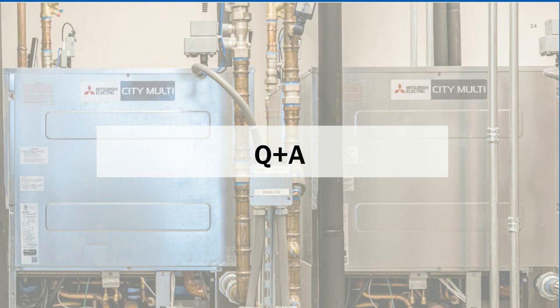So just to be a little more specific, if we're not talking about the well portion of the system, and we're just talking about the water to refrigerant portion of the water source system, you're looking at a similar life expectancy to the air source system. So 15 to 20 years on average is what we expect to get out of those portions of the heat exchangers. A lot of times we see them operating longer than that.